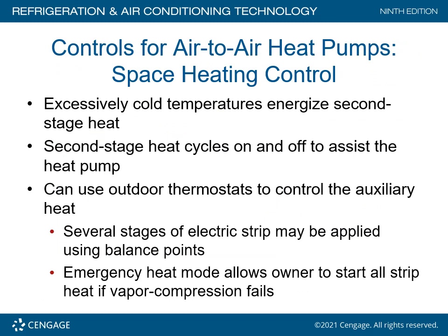Controls for air-to-air heat pumps, space heating control. Excessive cold temperatures energize the second stage heat. Second stage heat cycles on and off to assist the heat pump. Can utilize outdoor stats to control the auxiliary heat. Several stages of strip heat may be applied utilizing the balance points.